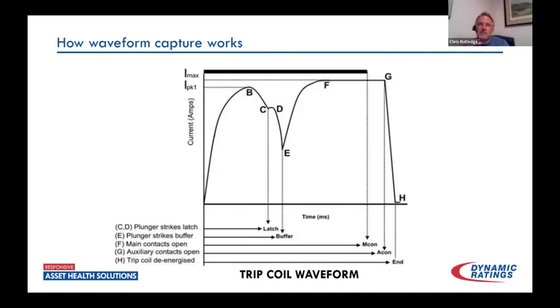Generally, two or three milliseconds variation is pretty normal after testing a lot of breakers for a lot of years. When you start seeing slowdown rates more than that, you're starting to have a problem. And again, this is not an outage problem at this point, but left unaddressed it will not only cause outage time, but also really rob your transformers of their life as well.